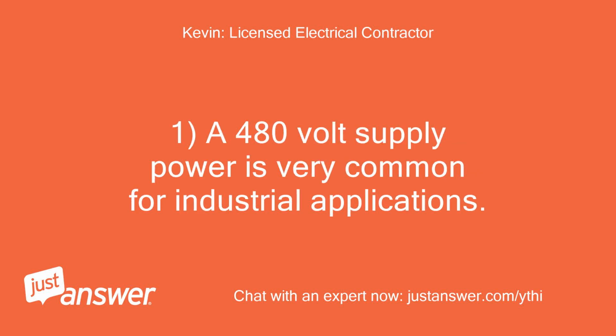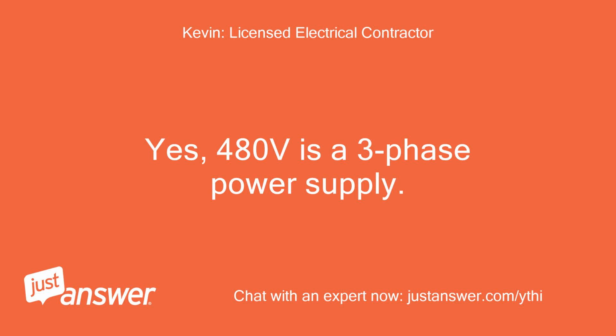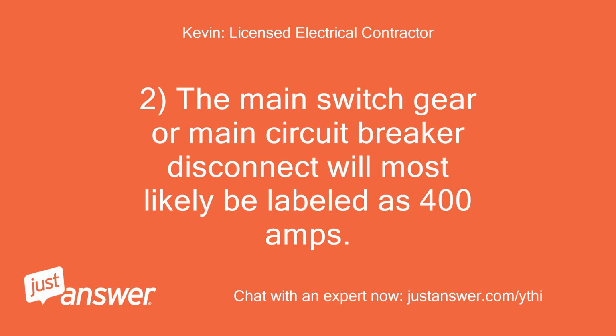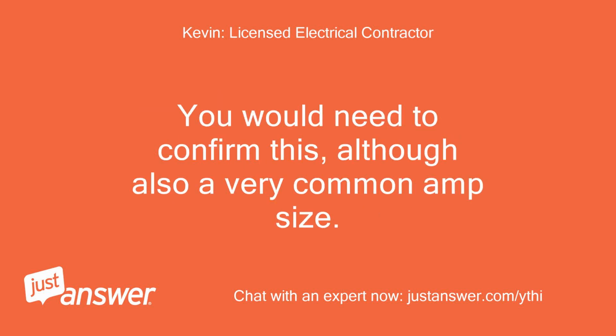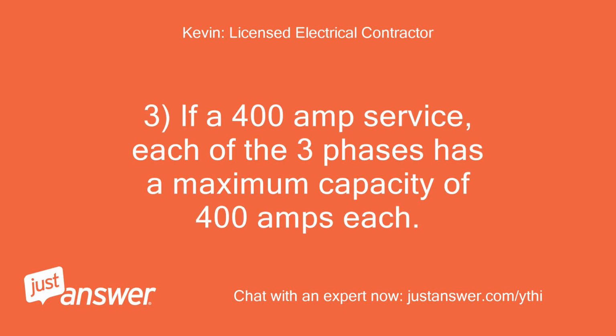1. A 480-volt supply power is very common for industrial applications. Yes, 480 volts is a 3-phase power supply. 2. The main switch gear or main circuit breaker disconnect will most likely be labeled as 400 amps. You would need to confirm this, although also a very common amp size. 3. If a 400 amp service, each of the 3 phases has a maximum capacity of 400 amps each.